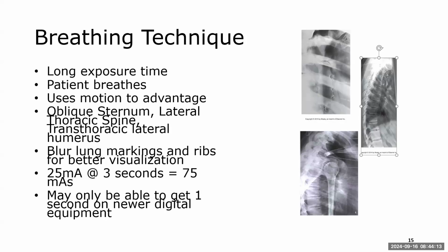Very, very low, and again, this is if your equipment allows you to do that. The way we would do that with our Siemens room is we would have a mAs value in mind, whatever our mAs value would be for these parts. We would set our mAs, and then for the exposure time that's right below it, what would we do to that exposure time? Run it way up, right? We could run it as high as it'll go.